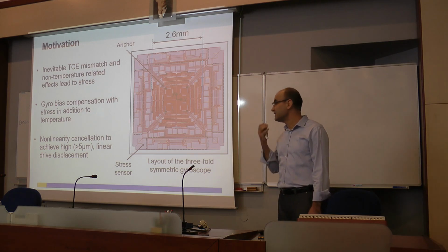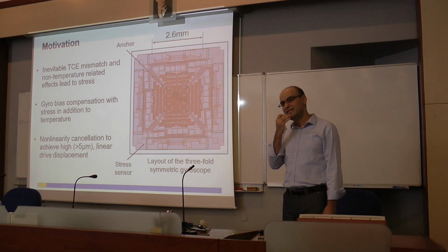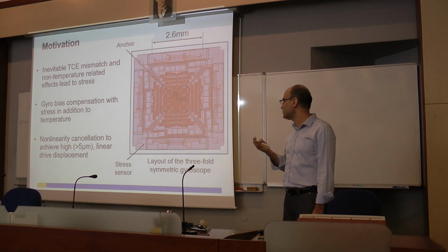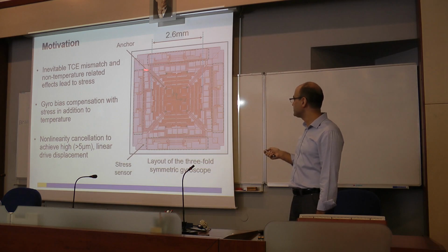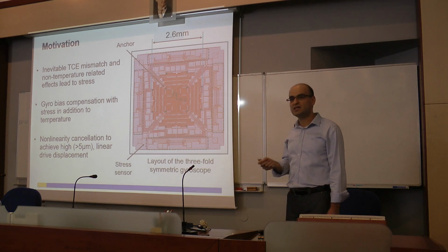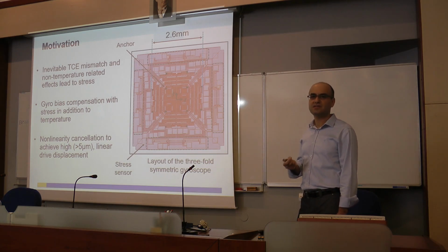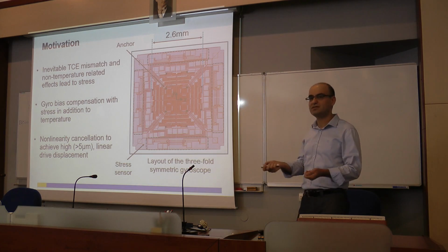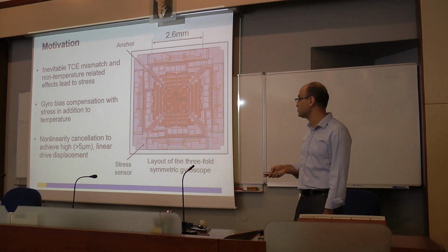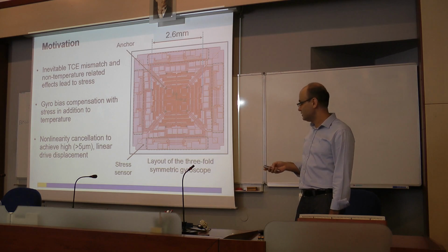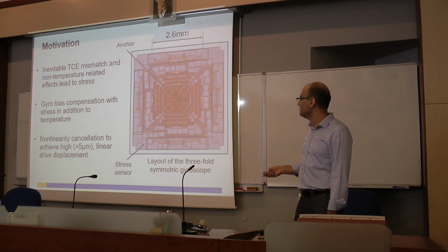The other thing I studied was non-linearity. I will explain this to you. This device operates by displacing in X or Y, and the more it displaces, the better signal-to-noise ratio you get. But as you increase the displacement, you run into certain issues. One of them is non-linearity.